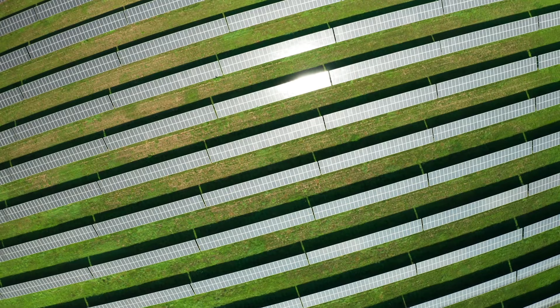And then the dispatchable plants, the coal and gas and nuclear plants that can run through the night, have to carry the entire load until solar comes back the next morning. Except that 122,000 megawatts of those plants are being retired. And the blackouts that occurred in 9 states last December happened precisely because this transition is not being managed at the pace that reality demands. Utilities have already reversed or delayed the retirement of 16,000 megawatts of coal capacity since 2022 because the grid cannot afford to lose them yet.